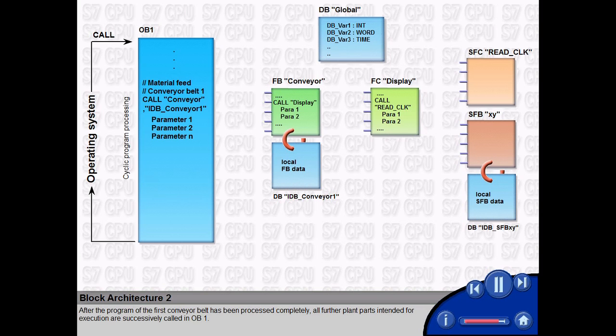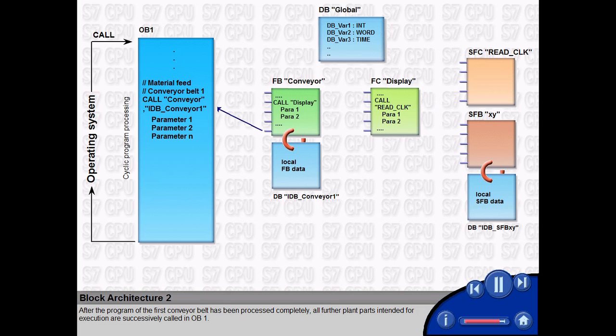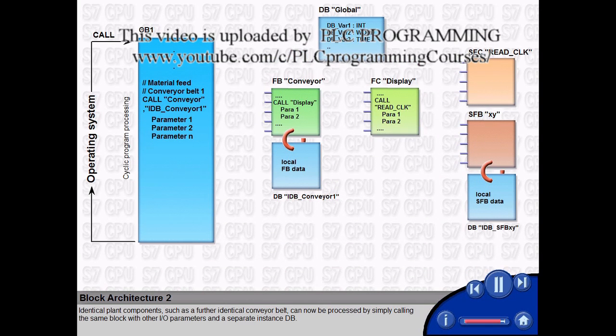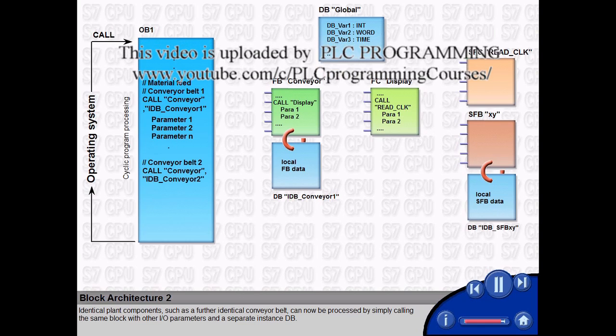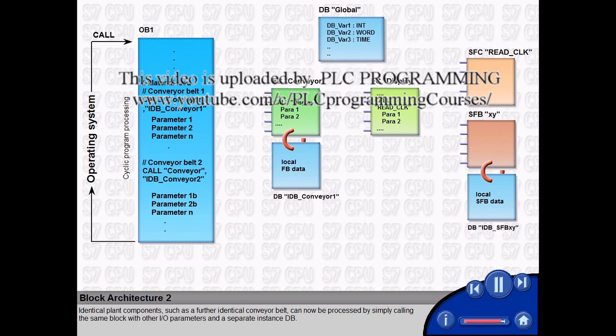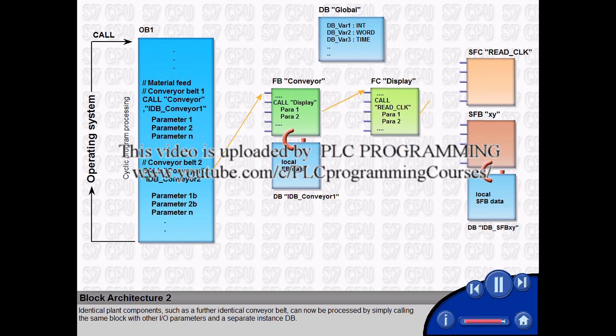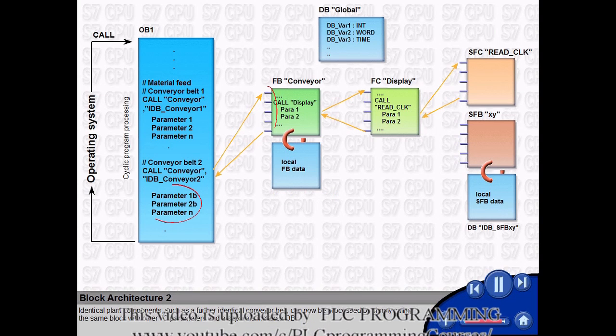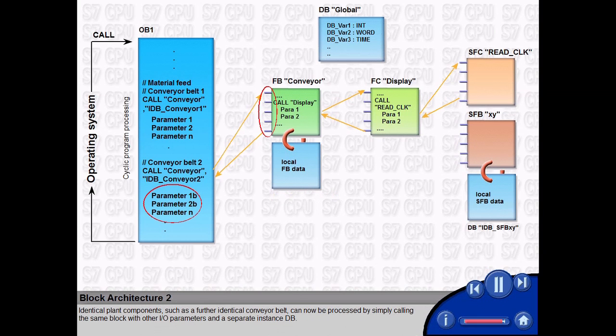After the program of the first conveyor belt has been processed completely, all further plant parts intended for execution are successively called in OB1. Identical plant components, such as a further identical conveyor belt, can now be processed by simply calling the same block with other I/O parameters and a separate instance DB.